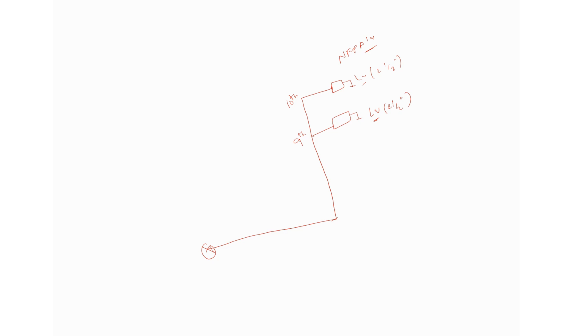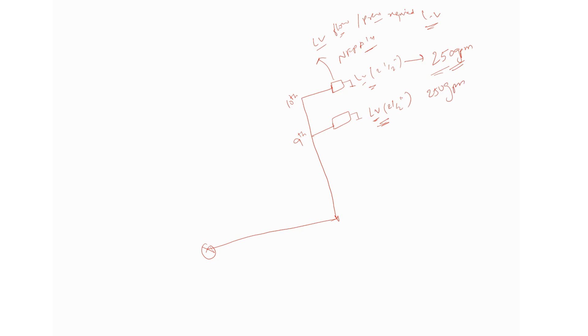There are two key points to remember. First point is related to flow from each landing valve, and second point is related to the pressure required at each landing valve. As I told in my previous slide, for 2.5-inch hose or landing valves we need to have 250 GPM as per NFPA 14. Since we are considering two landing valves, our calculation demand will be 250 GPM plus 250 GPM, which equals 500 GPM.